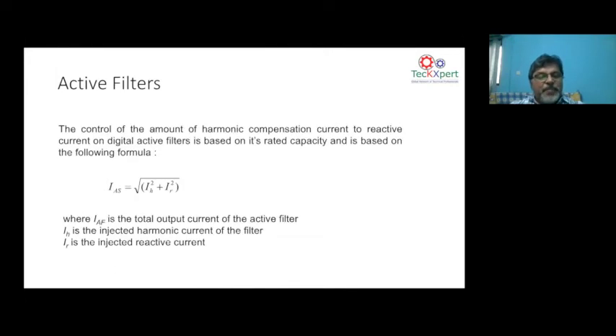Go to the next. Now, when you take the source current, it has two aspects. This is the IAF. Sorry, IAF is the active filter current. Active filter current you can split into two parts: harmonic frequency currents and reactive current. So, square root of IH square plus IR square. Go to the next. It explains a bit.